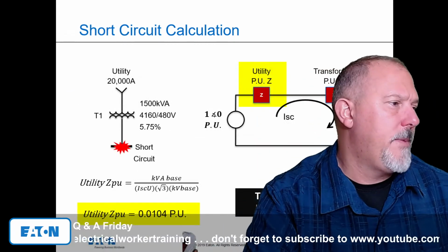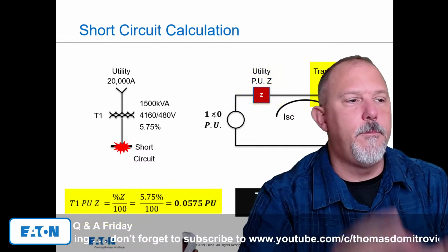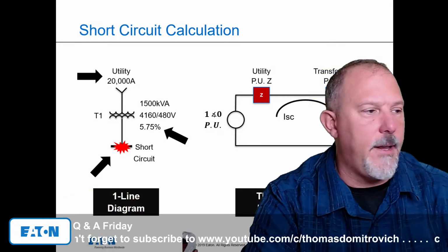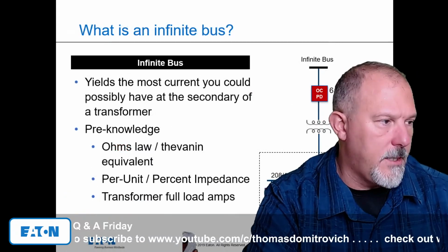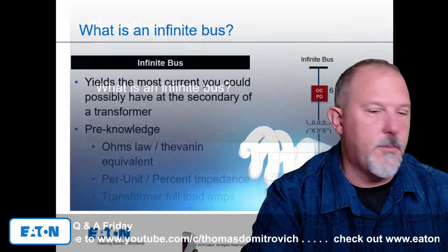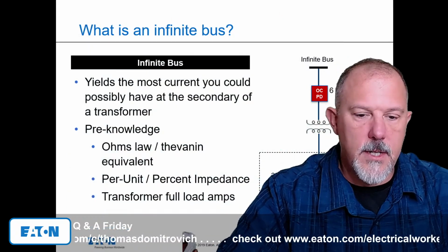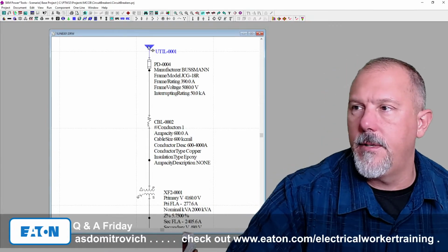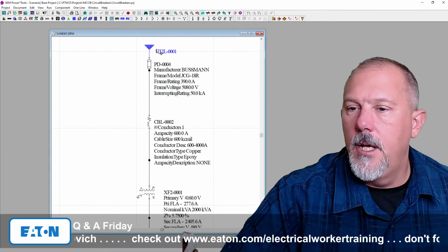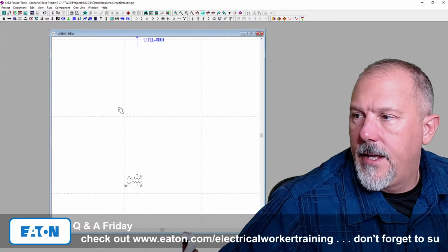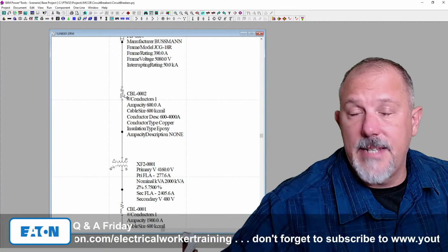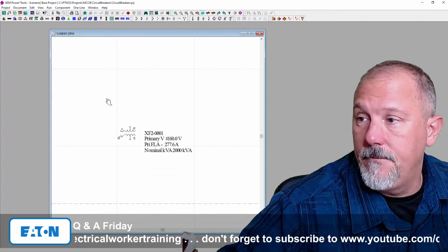It's not there. Not sure where it's at, but there are some IEEE standards that'll give you some ballpark figures, and 8 is not an unrealistic number from a utility perspective. So 8's not a bad number. Then I have a conductor. I have the primary, and I put a conductor length in there just primarily to satisfy SKM.